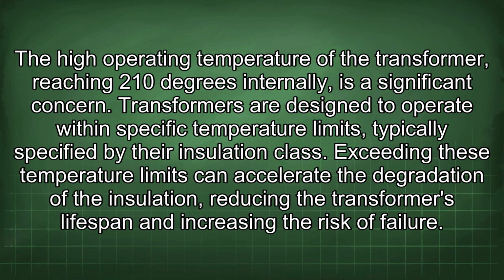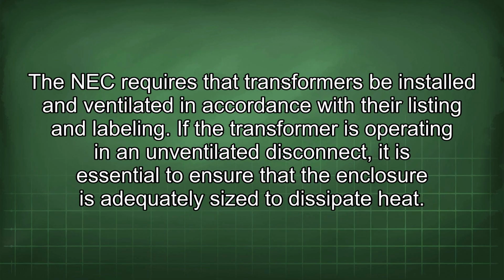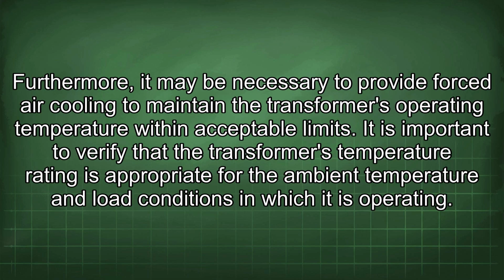The high operating temperature of the transformer, reaching 210 degrees internally, is a significant concern. Transformers are designed to operate within specific temperature limits typically specified by their insulation class. Exceeding these temperature limits can accelerate the degradation of the insulation, reducing the transformer's lifespan and increasing the risk of failure. The NEC requires that transformers be installed and ventilated in accordance with their listing and labeling. If the transformer is operating in an unventilated disconnect, it is essential to ensure that the enclosure is adequately sized to dissipate heat. Furthermore, it may be necessary to provide forced air cooling to maintain the transformer's operating temperature within acceptable limits.